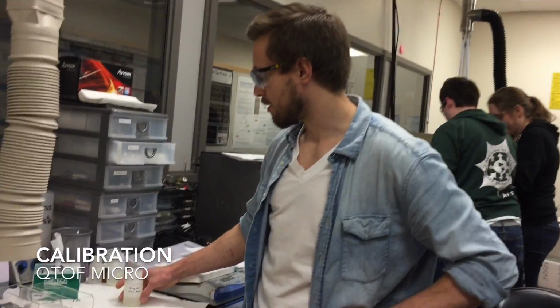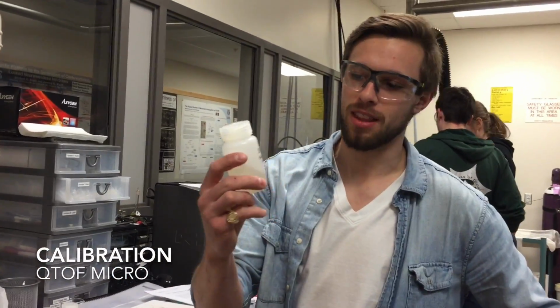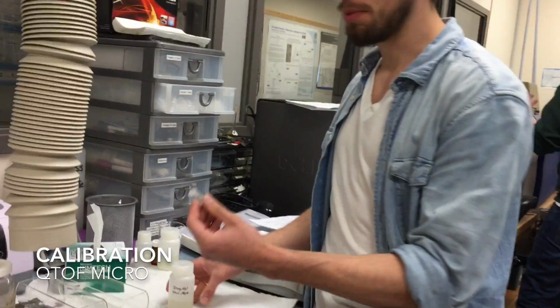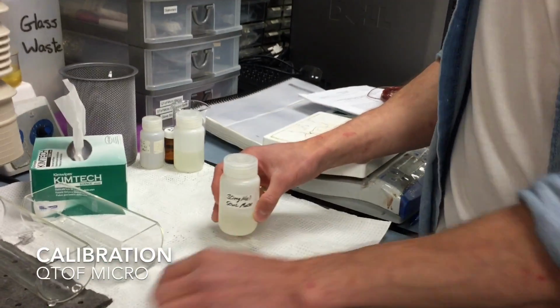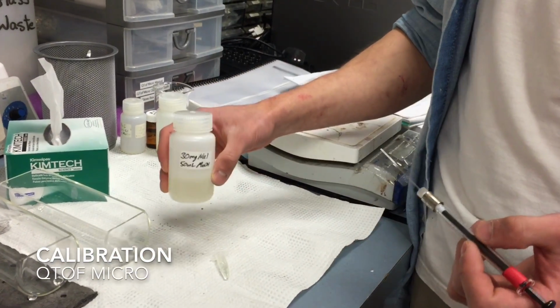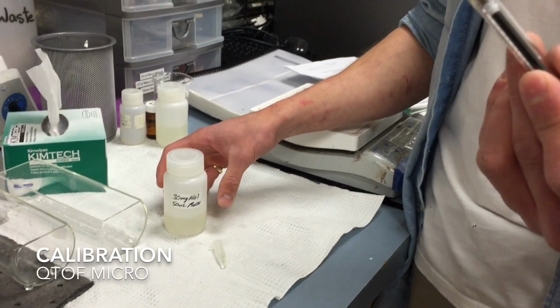Hello. Today we're going to learn how to calibrate the QTOF micro instrument using a solution of sodium iodide and methanol. The first important part is to not directly use your syringe from the calibration solution, as it contaminates it from whatever might be in there.